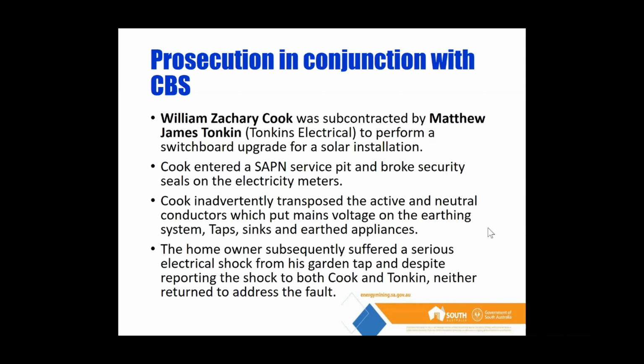Luckily, the homeowner actually had wooden floorboards, so when he touched his sink, whilst it gave him a heavy-duty blow, it wasn't enough to throw him to the ground. However, when he went outside and touched his garden tap, it was a different story. So, long story short, the homeowner then contacted both the Cook and Tonkin, and neither of them actually returned to the address to fix the fault or further investigate the fault. So he rung up SA Power Networks, and then SA Power Networks put it onto us.